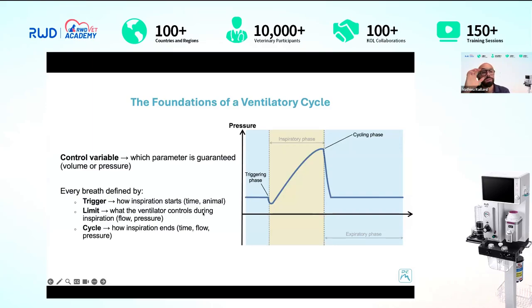The third parameter to consider in the ventilatory cycle is the limit. The limit is what the ventilator looks for during the inspiratory phase that would make us uncomfortable enough to discontinue the insufflation of the lungs. For example, if I set a tidal volume of 500 milliliters for a cat that is 3 kilos, of course, I realize that it is far too much and I'm going to make the lungs of this animal explode. But before this damage to the lungs, the pressures will go up quite a lot and quite markedly. The ventilator may perceive those pressures going up too much and may say at a limit, I'm not going to continue the insufflation up to 500 milliliters despite what the anesthetist has told me, because the pressures are too high. I'm going to stop there, and that is called the limit.